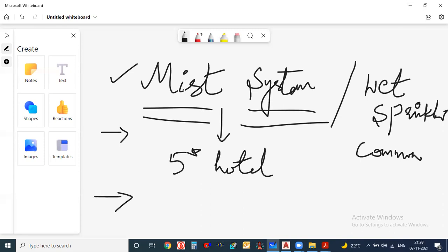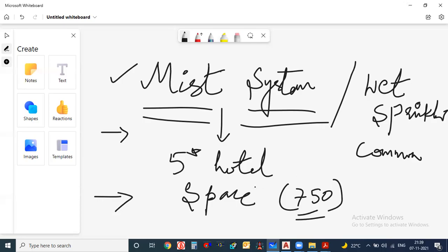There are also certain spaces which are preferable for the mist system. There is one document, NFPA 750, where you will learn a lot about the mist system. Certain spaces like the electrical room, generator room, and turbine room are mostly suitable for the mist system. The wet sprinkler system is a very general system, used in corridor areas, offices, residential spaces, and bedrooms.